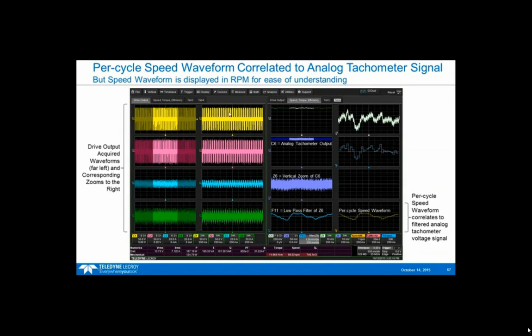This is the full 5-second acquisition here. These are the zooms. This highlighted area corresponds to this area for the zooms. Notice when I use the zoom and gate this way, everything's zoomed. So now my torque signal and speed signal are zoomed. This signal here is this signal, but also has a vertical zoom on top of it. This is my analog torque signal or tachometer signal for speed. I'm zooming both horizontally by looking at this area, and vertically by expanding that scale. You can see that here. If I look at Z6, that's 10 millivolts per division, where the original C6 waveform is 50 millivolts per division.